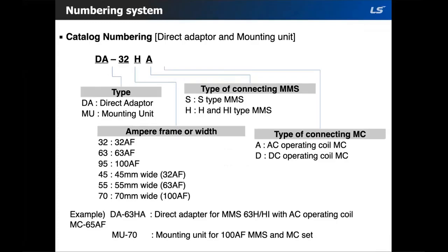So for example, if you need a direct adapter for MMS 63H with an AC operating coil, which would be MC 65 frame size, you would choose a DA-63, which would be your amperage frame size. And then you would go with the H, and then AC coil would be A. So that makes DA-63HA. And for the mounting unit, you don't have to worry about the type of connecting MMS type or the MC type. You would just go for MU dash the width size.